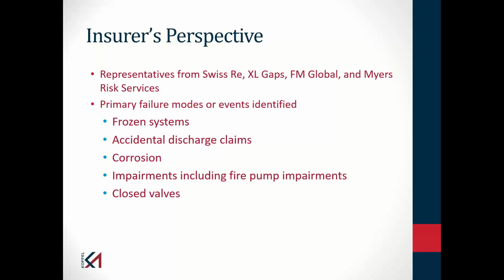So the attorney came back to me and said, oh, that's good news. I said, well, why is that good news? He said, well, we had a roof. So we're working for the owner of this warehouse. We had a roofing contractor in here, and they did some roofing work. And in order to do the roof work, they had to remove the sprinkler system. And I'm assuming that caused them to shut the sprinkler system. I said, yes, it probably did. If I removed the sprinkler system, I closed the valve. And I said, well, where was this work done? And he told me. And I said, well, yes, that's the valve that I found closed, and that's the area where this fire started.